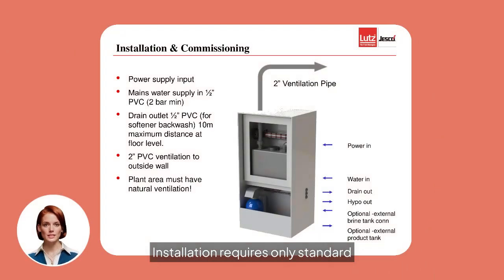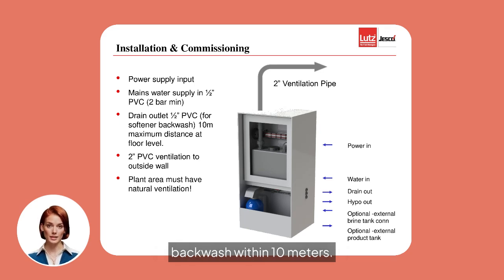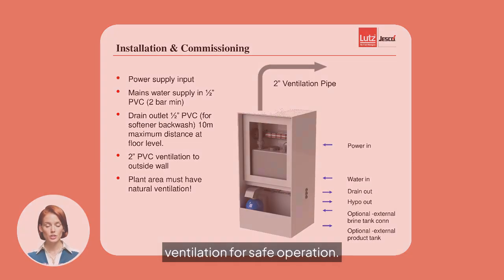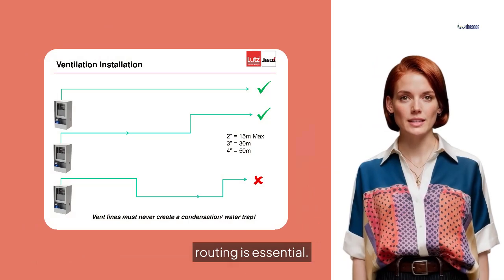Installation requires only standard utilities. Provide power, a mains water supply at a minimum of 2 bar, and a drain for softener backwash within 10 meters. A 2-inch PVC vent line must run to an outside wall, and the plant room must have adequate natural ventilation for safe operation. Correct ventilation routing is essential.